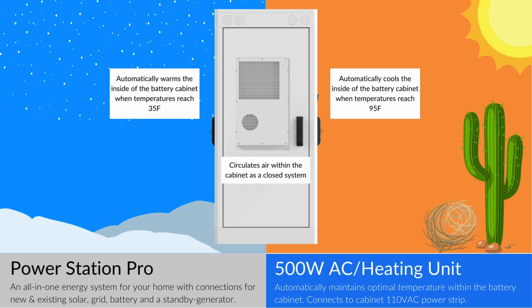This increases the scope of how you can use this system for really hot or really cold climates. The unit comes with integrated Freon, which would turn on at certain temperatures and keep the battery cabinet at optimal temperature. And then when it's within the optimal range, it still circulates air, but it does so in a closed system.